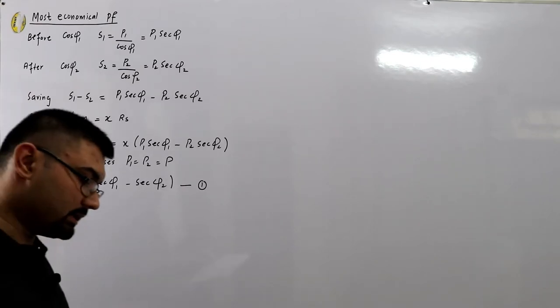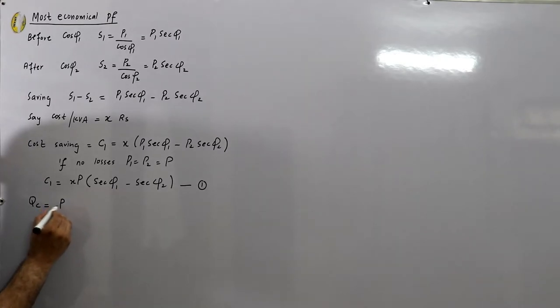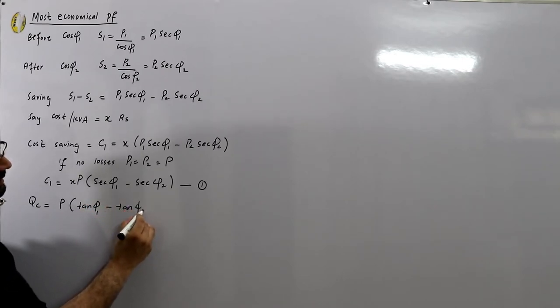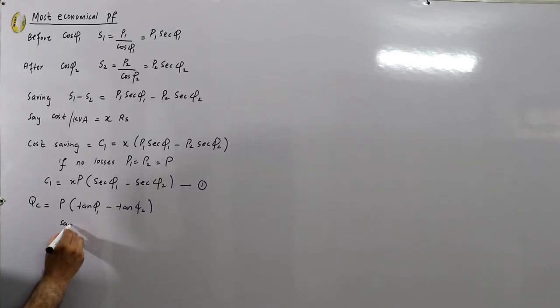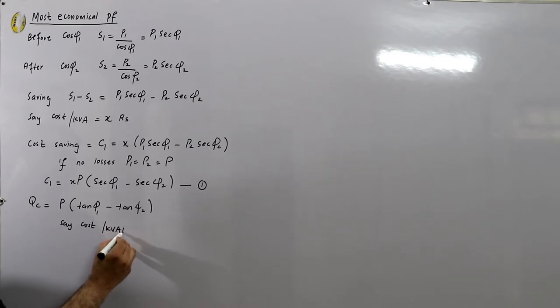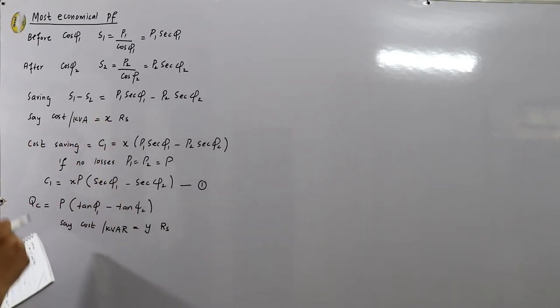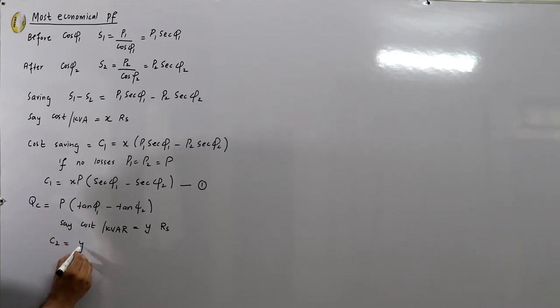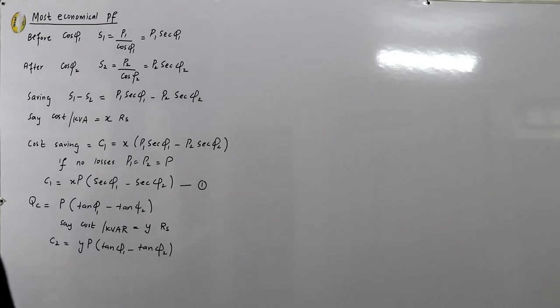The leading kVAr required from the capacitors being installed is P × [tan(φ1) − tan(φ2)], where φ1 and φ2 are the power factor angles. If the cost per kVAr of the capacitance improvement devices is Rs. Y per annum, then the annual cost C2 of those devices equals Y × P × [tan(φ1) − tan(φ2)].